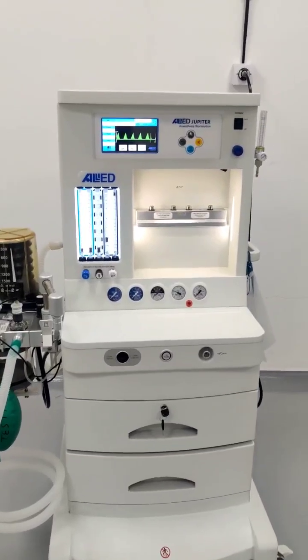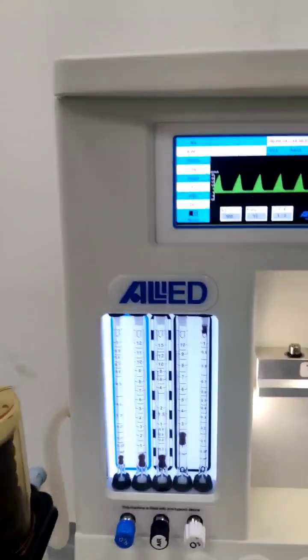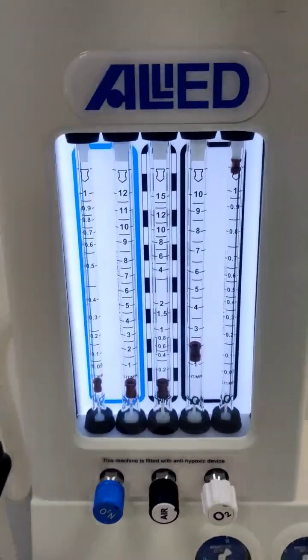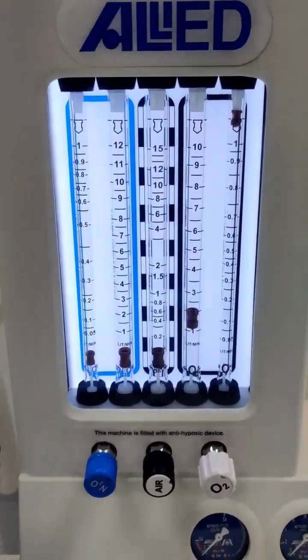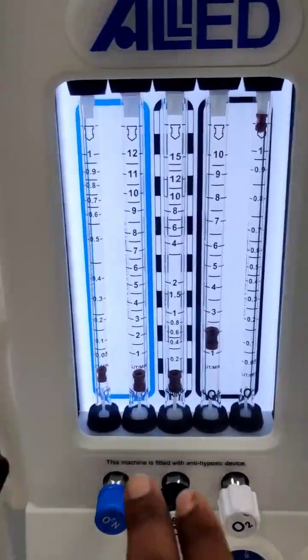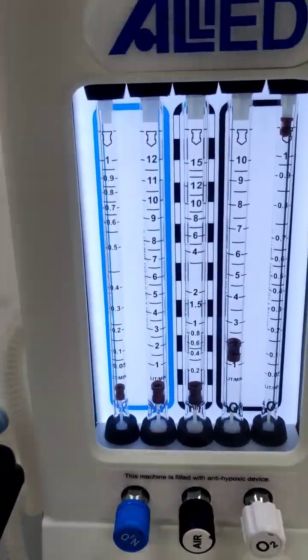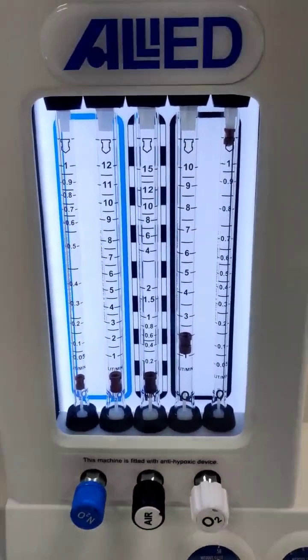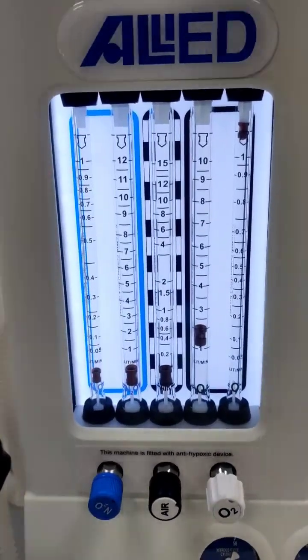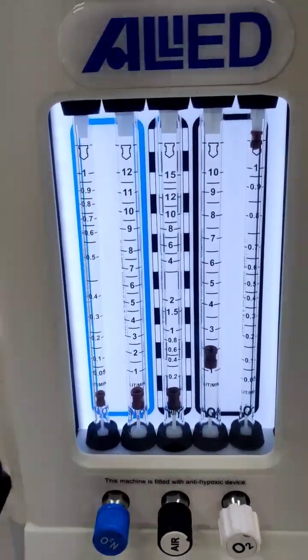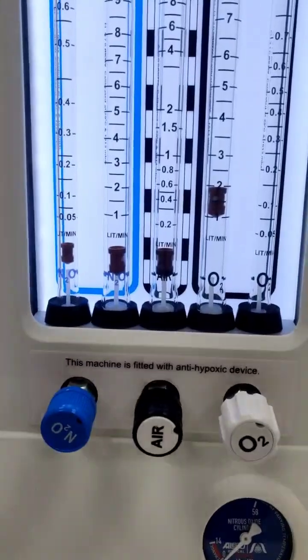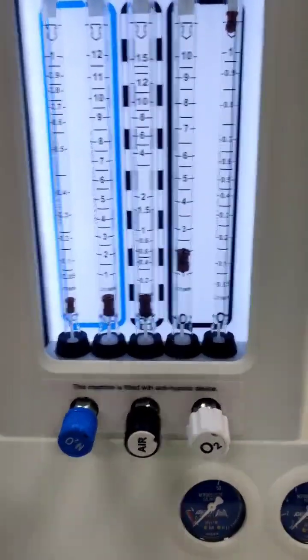Now coming on to the front side of the machine, as I mentioned earlier, this is a 3-gas machine, so we are giving 5 tube rotameters in this. Two for nitrous oxide, these are the flow tubes for setting the nitrous oxide flow. These are the 2 tubes for setting the flow of oxygen, and the center one is for the air. So we have dedicated knobs for controlling the flow of each gas.